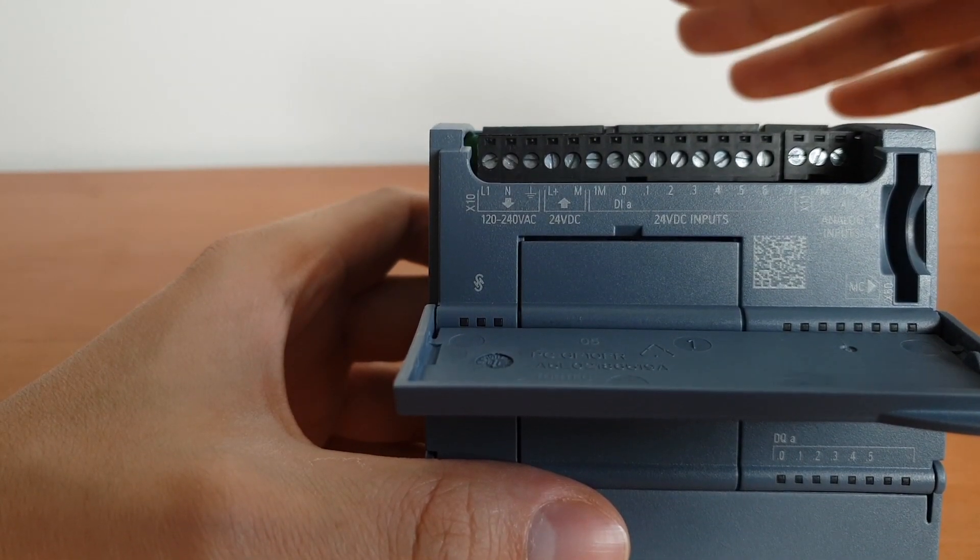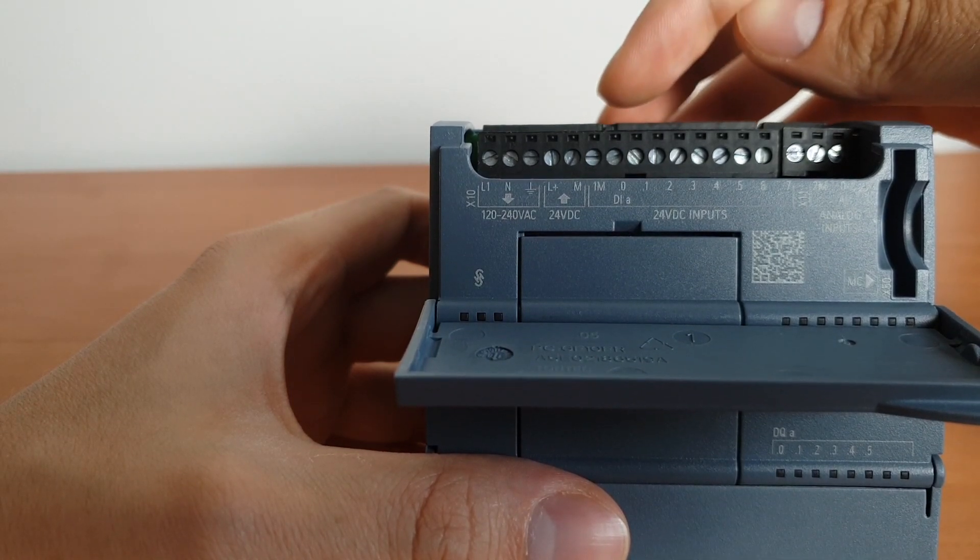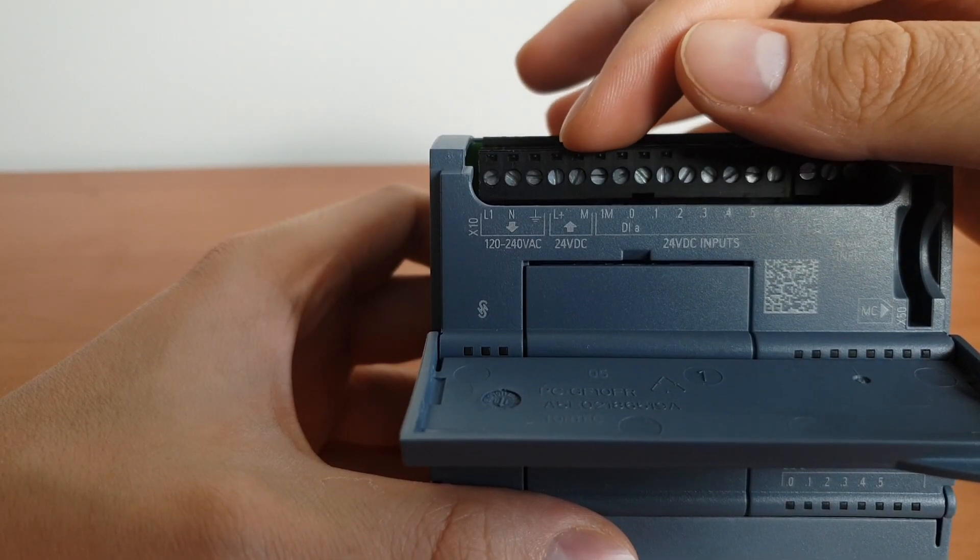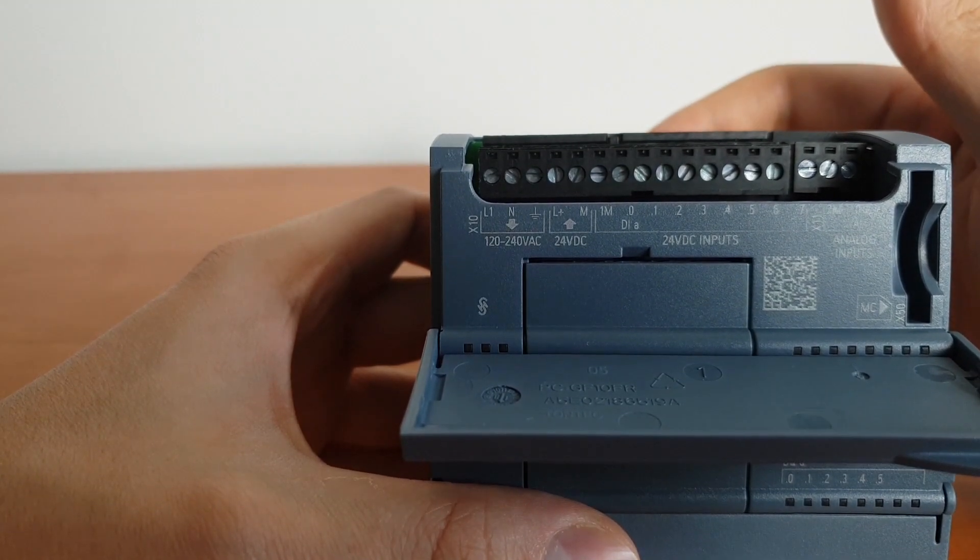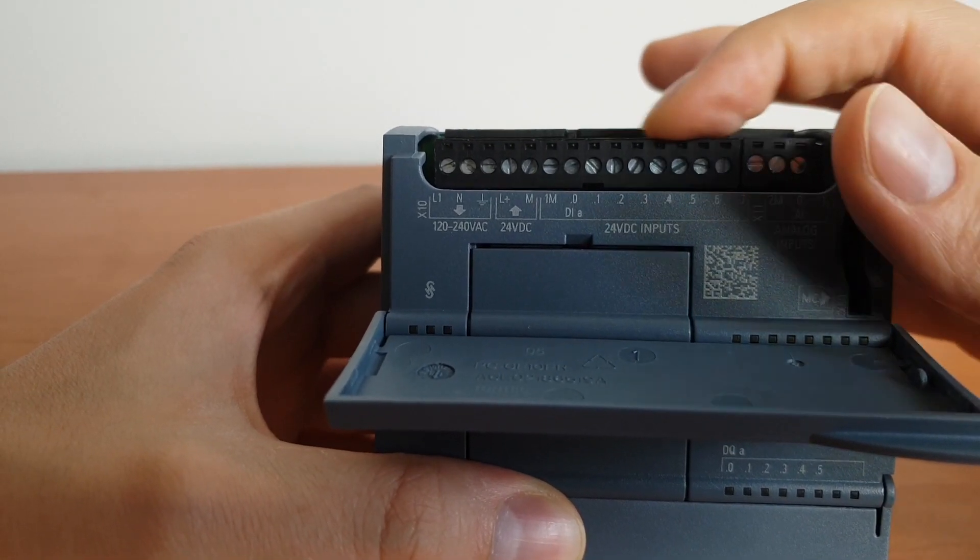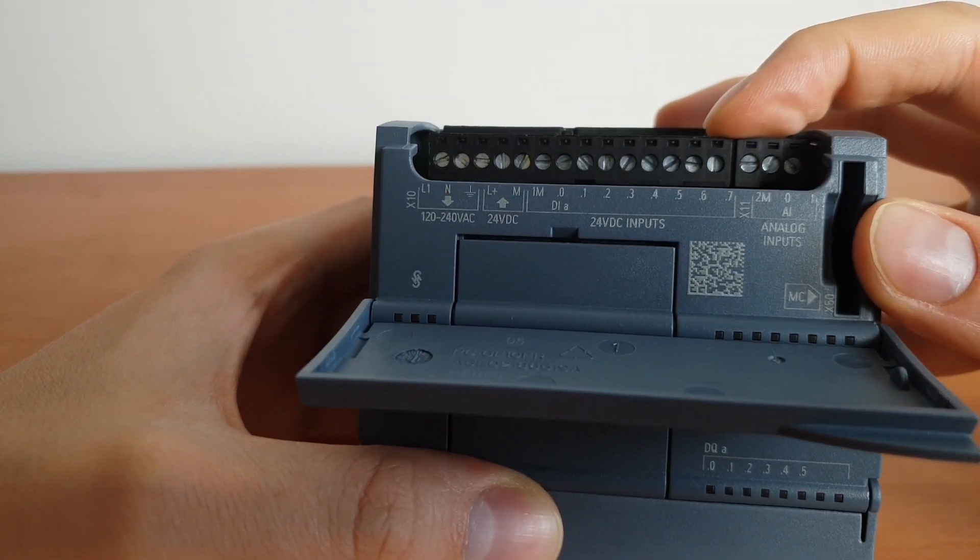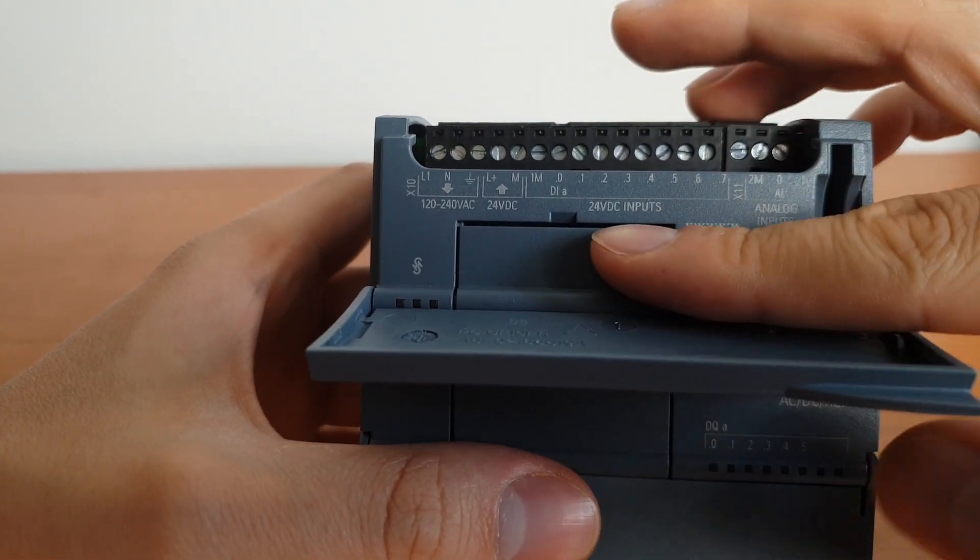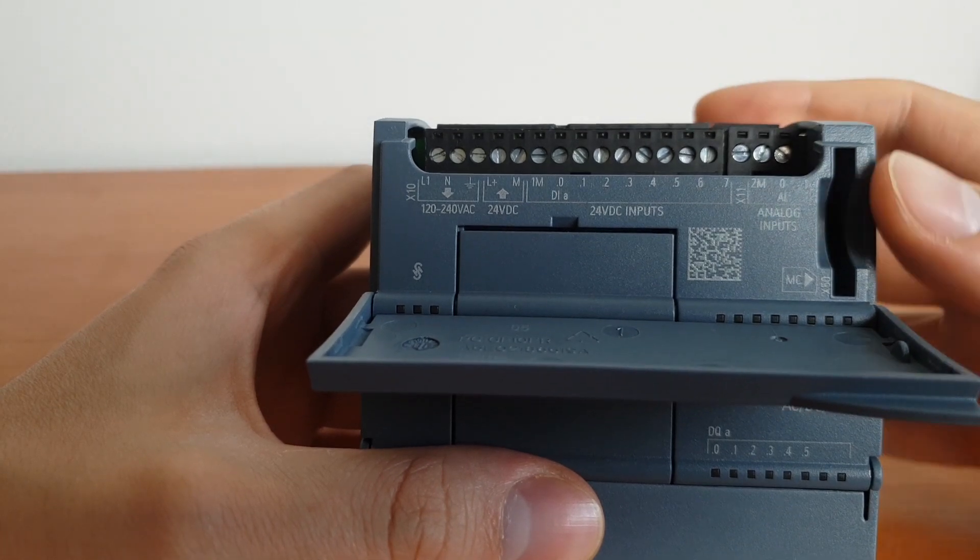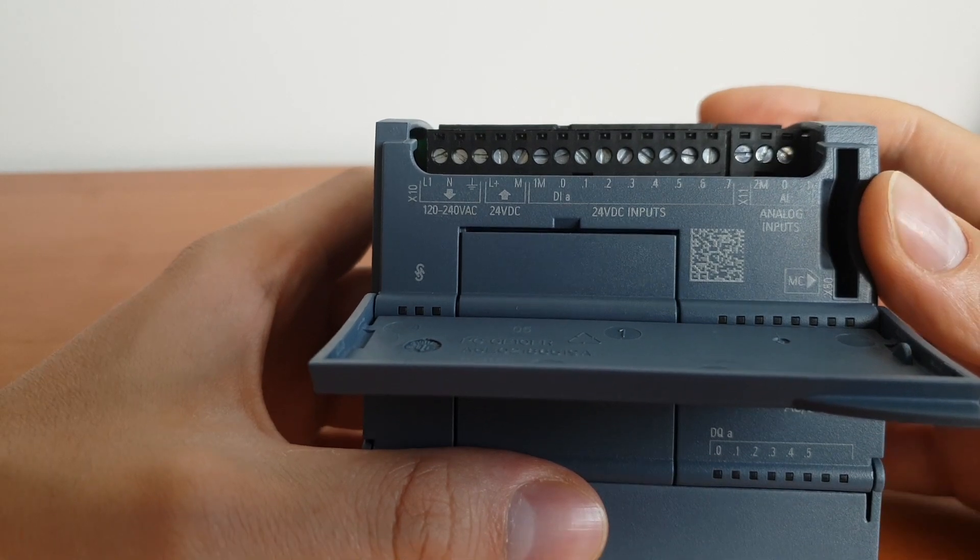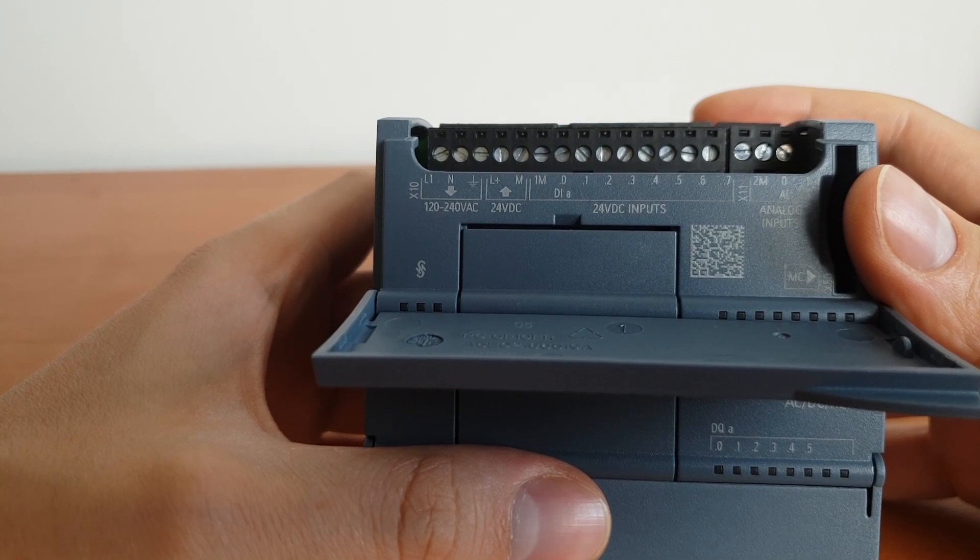Most of the sensors that you will see, all the lamps, buttons, pretty much anything, will be powered by 24 volts DC. There's 24 volts DC here with an arrow pointing up, which means we could power up some sensors from this PLC. Next thing here is this part of the panel which is for 24 volts DC inputs. Whenever there is 24 volts coming inside, the PLC will interpret it as a one on this input. Whenever it's zero volts, the PLC will interpret it as zero or false.